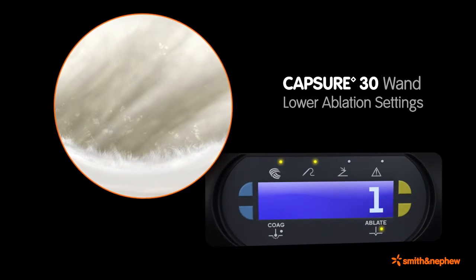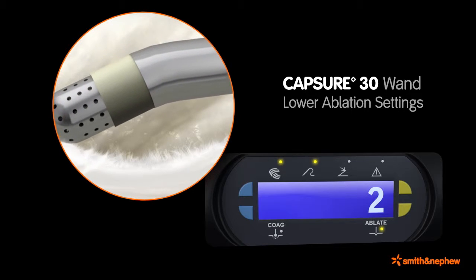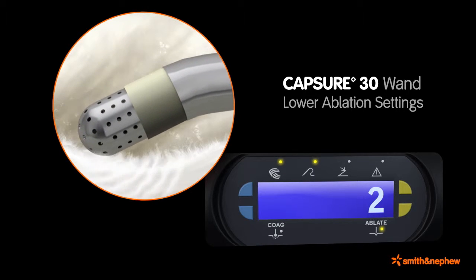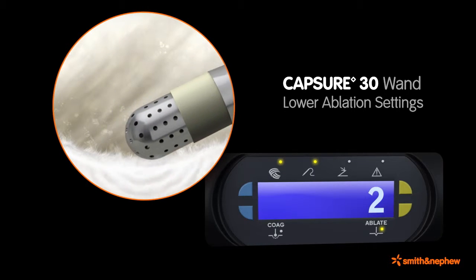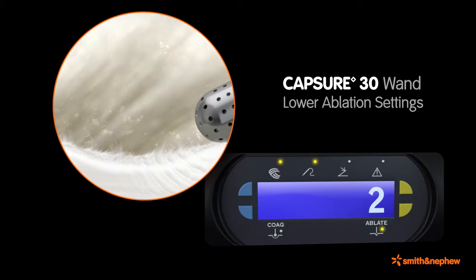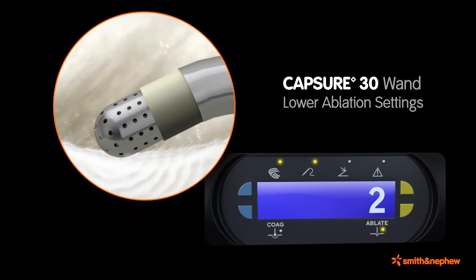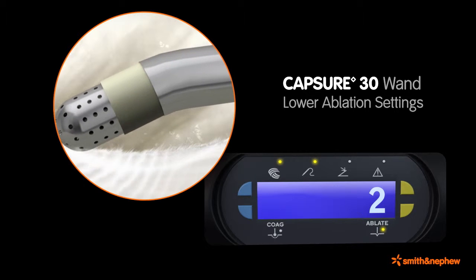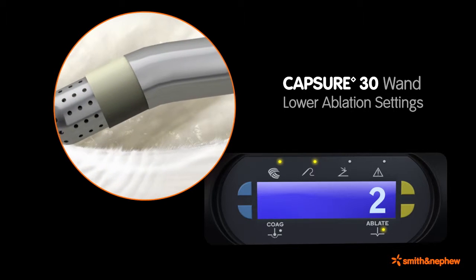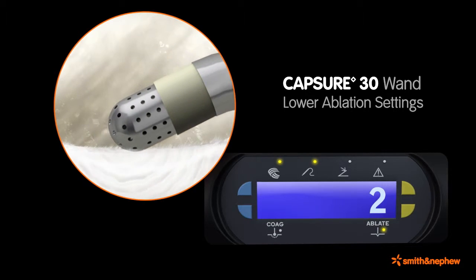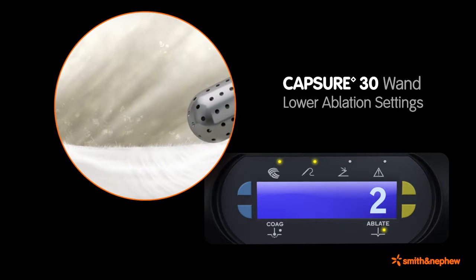At lower settings, the saline solution is merely heated by Joule dissipation as the electrolyte ions moving in the solution respond to the imposed electrical field. Tissue containing collagen may shrink as a result of the heating. Only a select number of wands, such as Capsure, are recommended to be used at lower ablation settings.